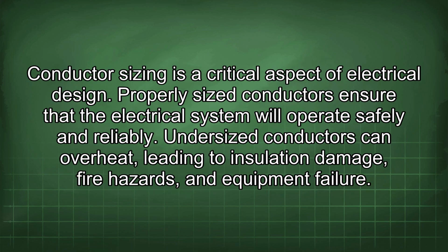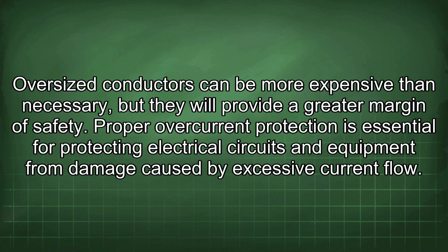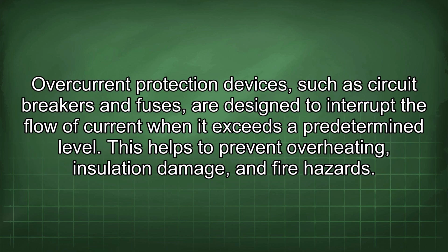Conductor sizing is a critical aspect of electrical design. Properly sized conductors ensure the electrical system will operate safely and reliably. Undersized conductors can overheat, leading to insulation damage, fire hazards, and equipment failure. Oversized conductors can be more expensive than necessary, but they will provide a greater margin of safety. Proper overcurrent protection is essential for protecting electrical circuits and equipment from damage caused by excessive current flow. Overcurrent protection devices, such as circuit breakers and fuses, are designed to interrupt the flow of current when it exceeds a predetermined level. This helps to prevent overheating, insulation damage, and fire hazards.